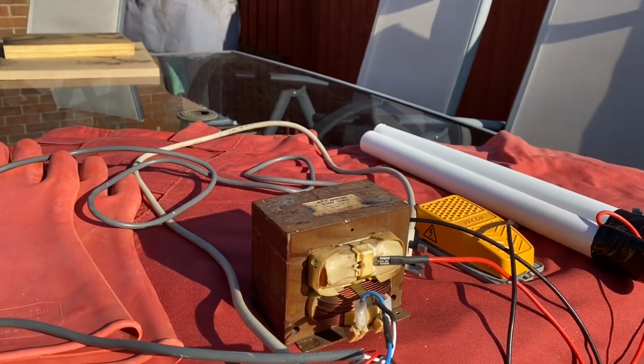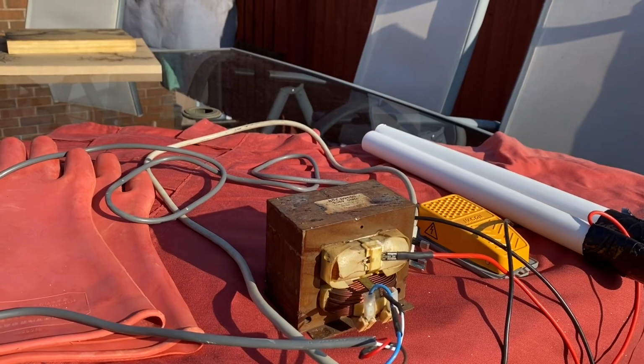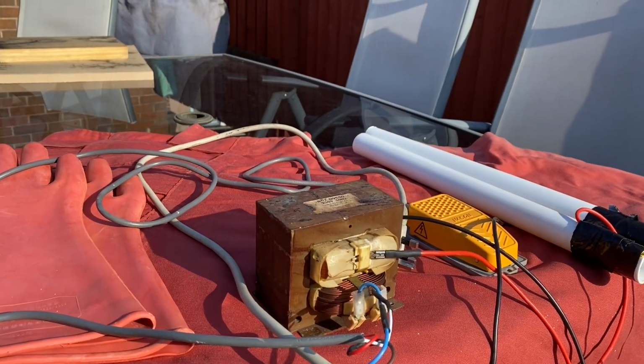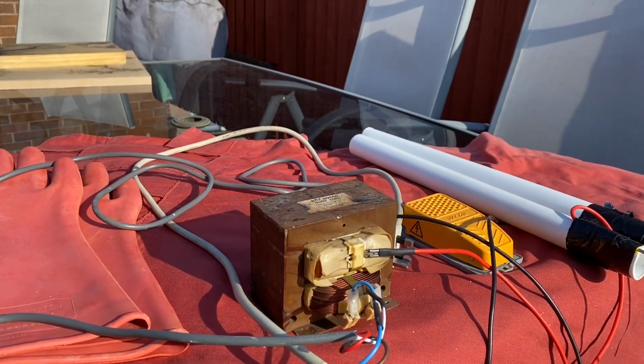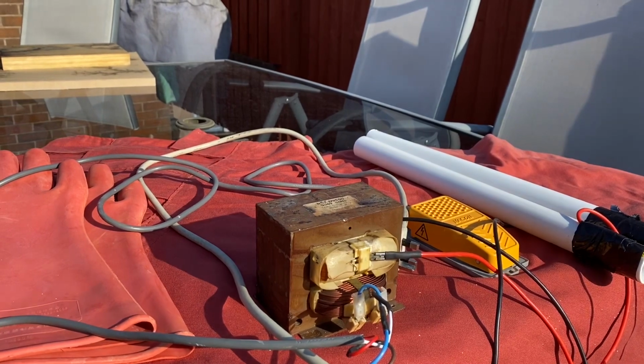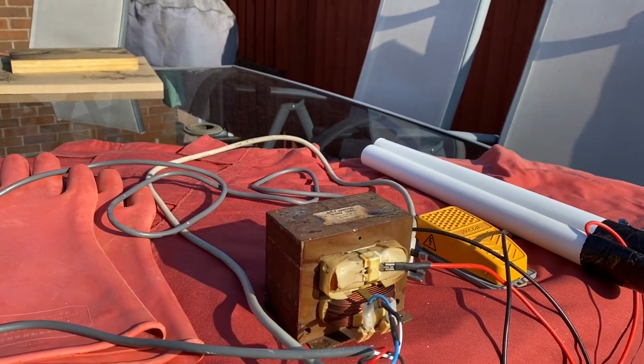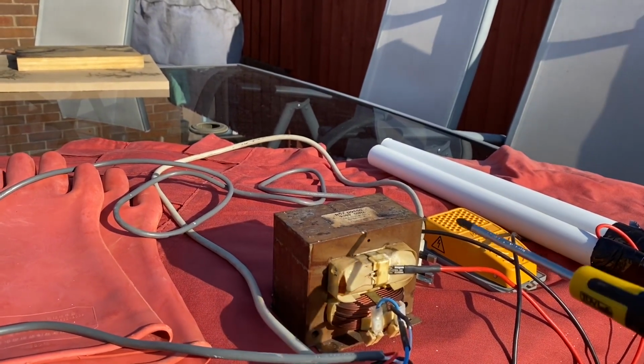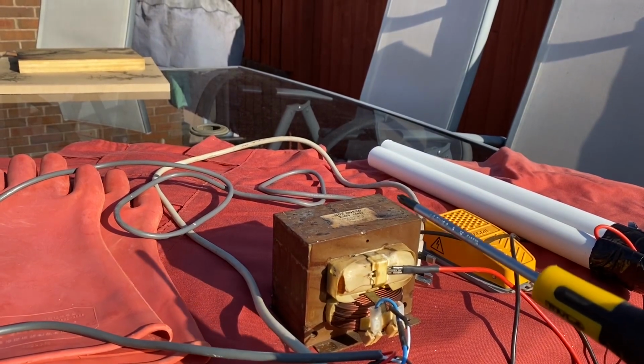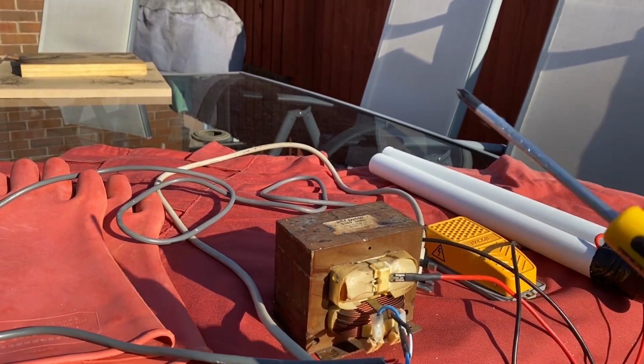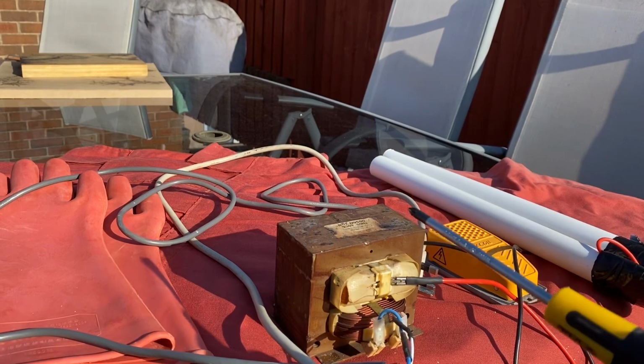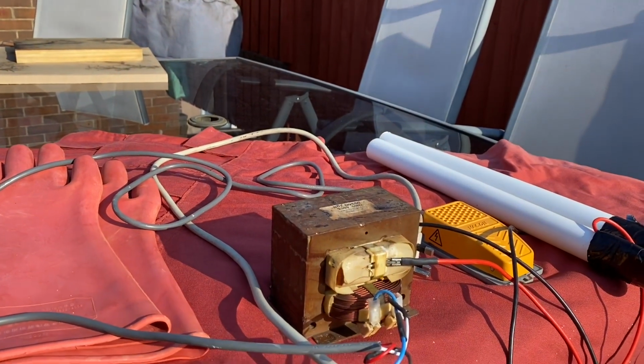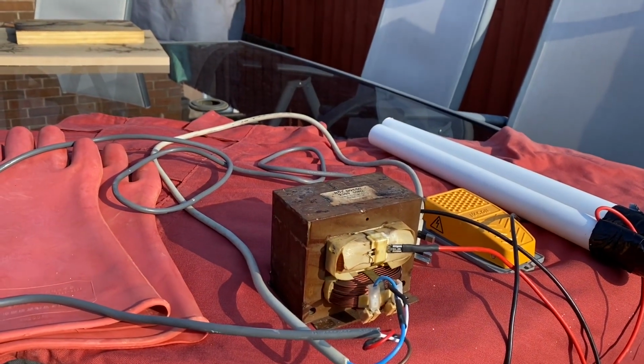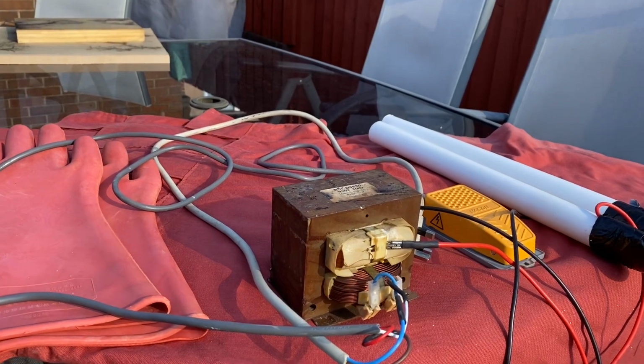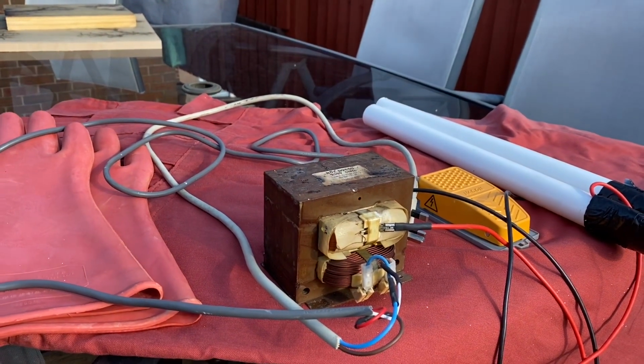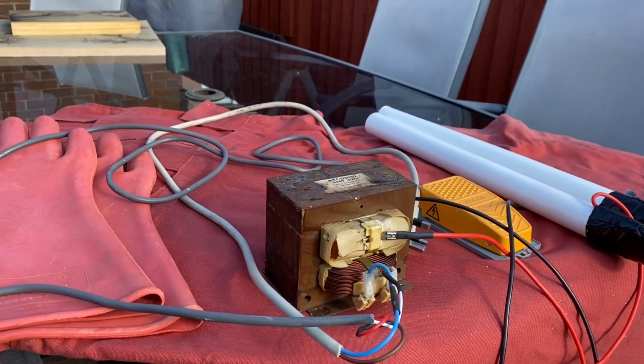This is also dangerous because it only takes about 100 volts at roughly 50 milliamps to stop your heart. This transformer is kicking out over 2000 volts at 1 amp, so it's do not pass go, do not collect £200 - you'll be dead before you hit the floor if you touch this.